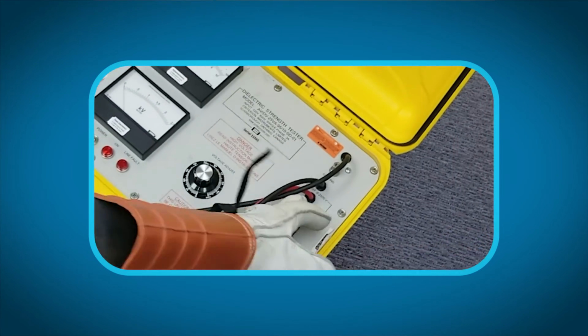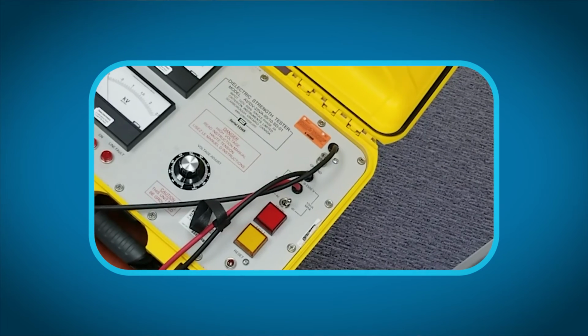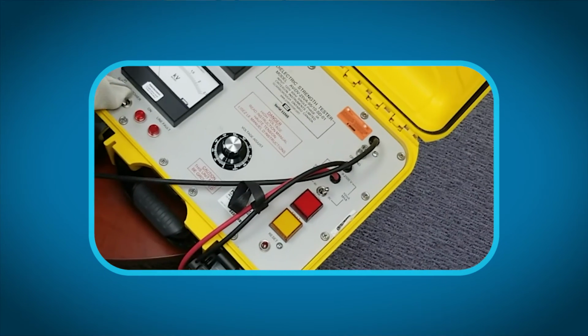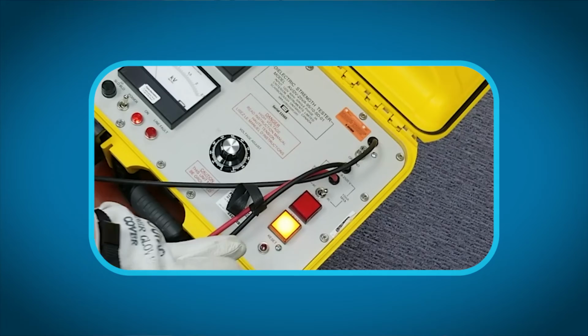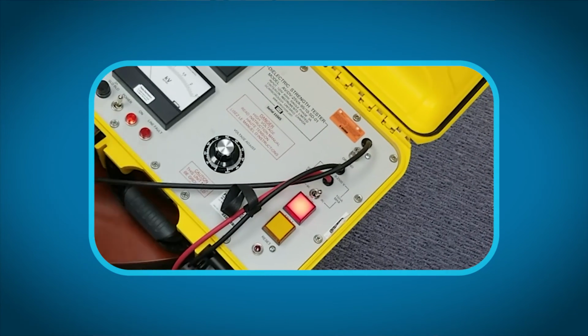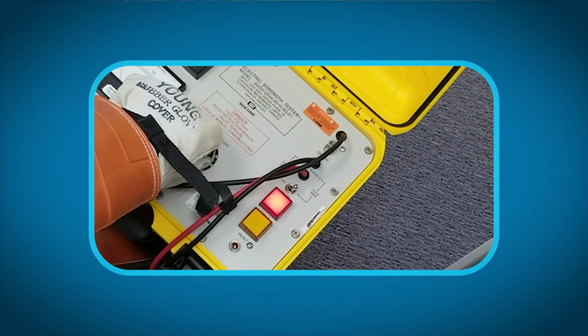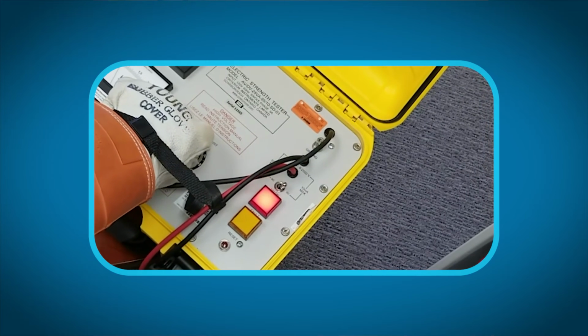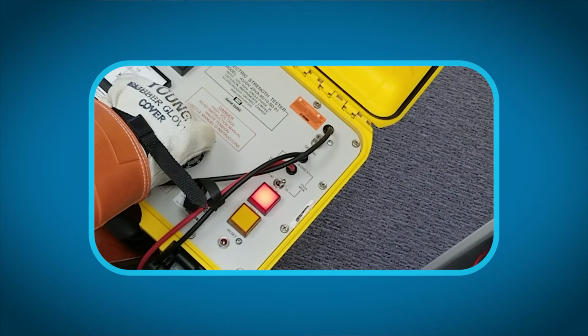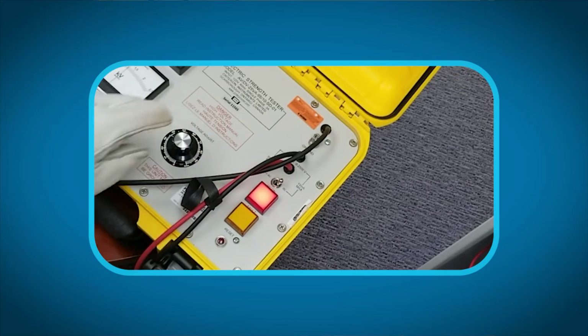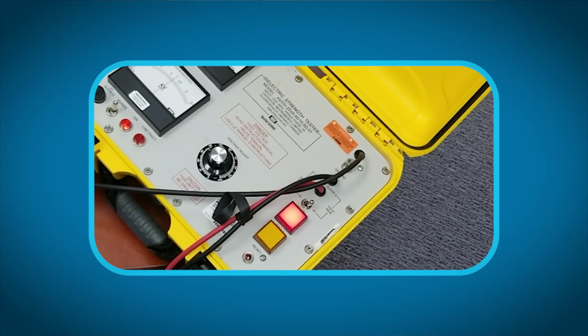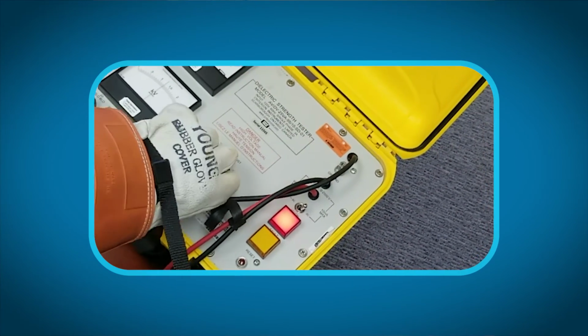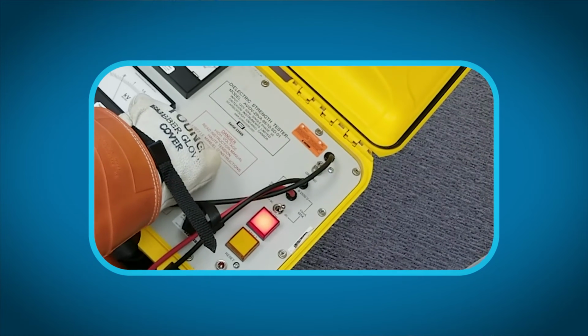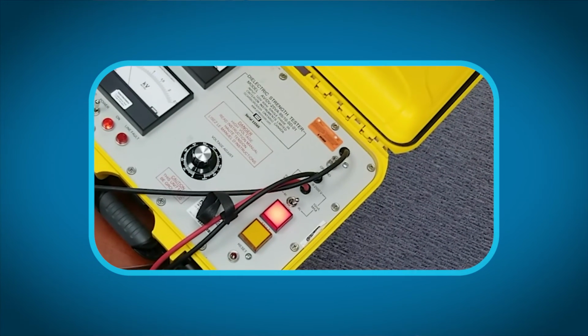Step 4. Turn HiPot tester on. Select the desired voltage type, AC or DC, press the reset button, and starting at 0 volts, raise the voltage at a rate of 200 volts per second or less until the test voltage is obtained, and hold for a period of 1 minute. Step 5. Gradually reduce the test voltage to 0 volts, then turn off and disconnect the tester.